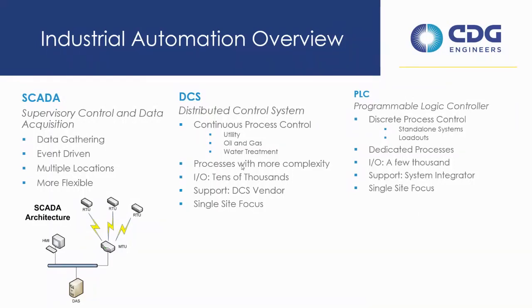SCADA came about because of accessing remote sites. In the utility industry, power utilities or wastewater treatment type sites, you have a lot of remote locations, typically just overcurrent protection or a small process like a pump station or lift station. Folks needed a way to get all that information back to a central location - that's how SCADA came about.